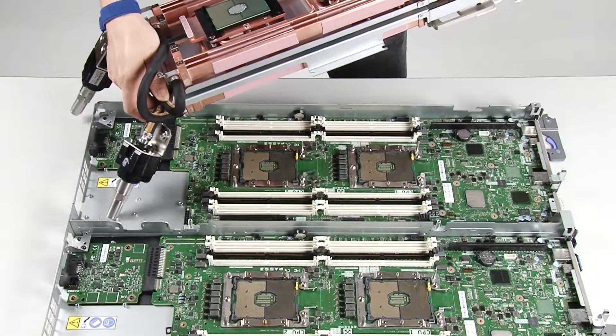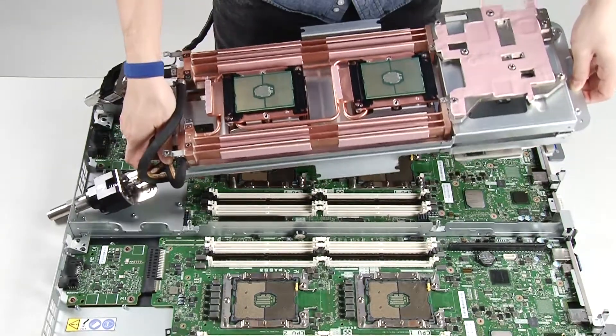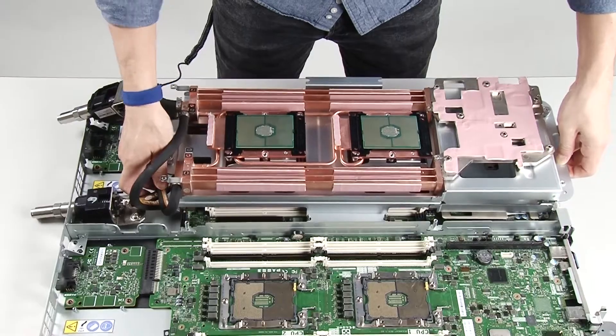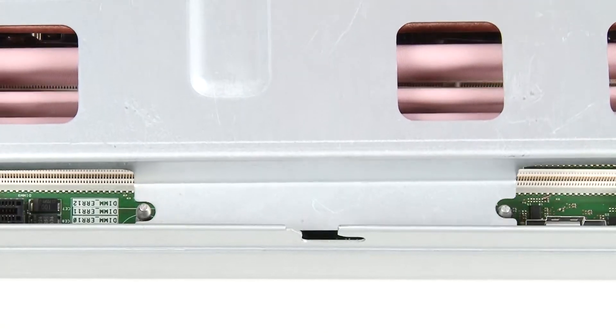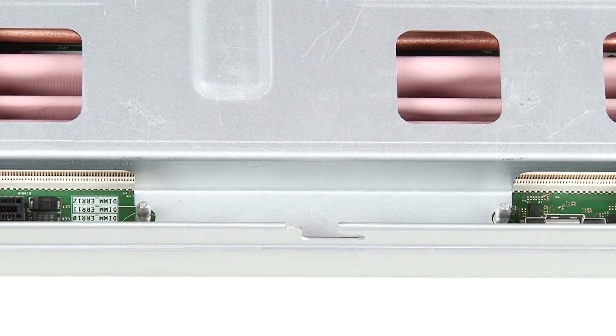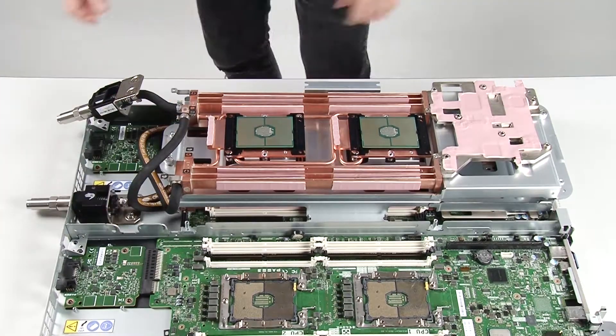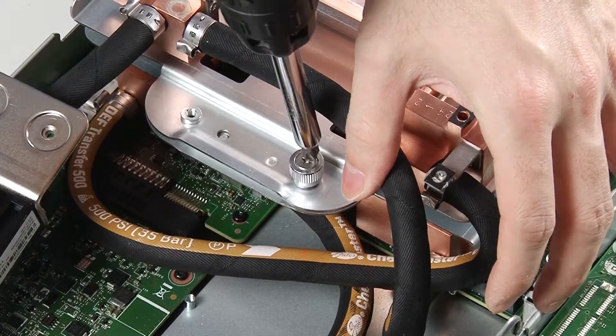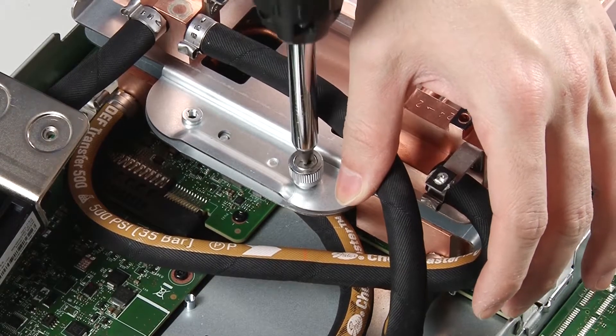While holding the water loop with both hands, angle rear downward and insert the quick connect tip through the opening in the rear of the tray. Align the water loop with two M.2 backplane guide pins on the system board. Gently lower the water loop onto the system board and ensure it is seated firmly. Tighten two captive thumb screws located at each end of the water loop carrier.